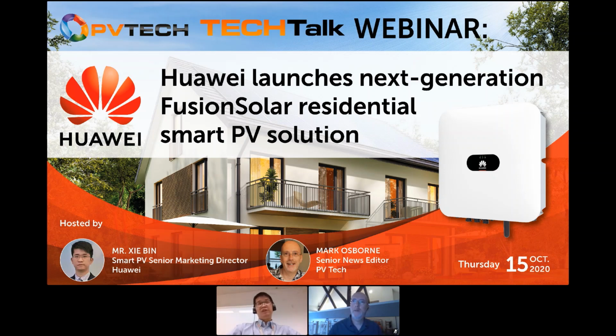Because conventional string inverters can't handle two different directions in one string, that approach isn't workable. But with Huawei's second generation residential solution, we support optional optimizer application. You just install several optimizers on small rooftops with 3 or 4 panels facing east or west, while the majority of the PV modules facing south don't need optimizers. This flexible application is workable with the second generation Huawei solution, giving installers maximized flexibility to meet different customer requests.